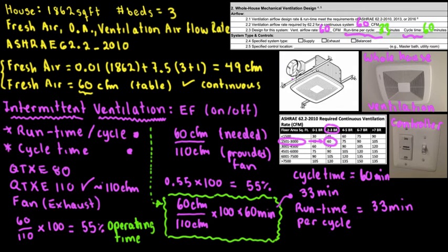And also one more thing, so we're taking into account the bigger exhaust fan, because the installation is not perfect. 99% of the time it's not perfect, because 110 CFM actually depends on the static pressure. So depending on the static pressure, this is at 0.10 external static pressure. So what is the static pressure?